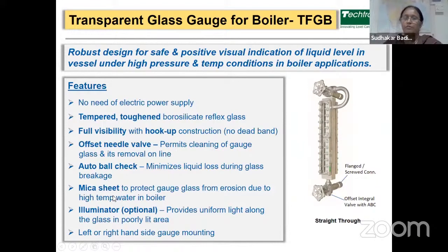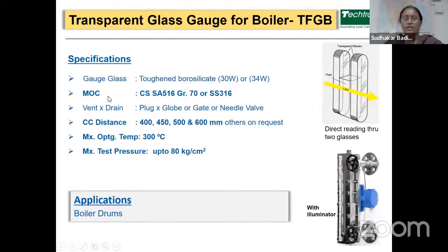This gauge can be provided with mica sheets to protect the gauge glass from erosion due to the high temperature water in the boiler. So this is the most advantage of this gauge. The illuminators can be provided for uniform light along its glass body in a poorly lit area. Again, right and left orientation gauge mounting is available. Material can be available in CS SA516 grade 70 or SS316. The standard CC distances are available as 400 mm, 450, 500 or 600 mm, and other CC distances are available on request.